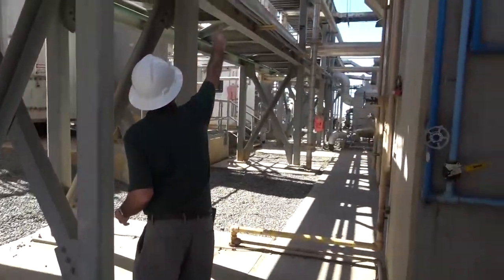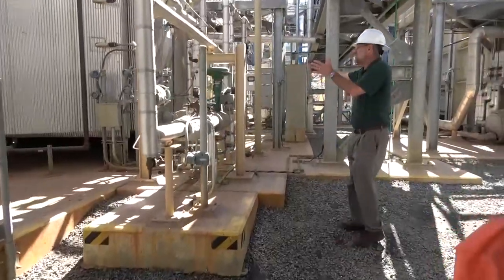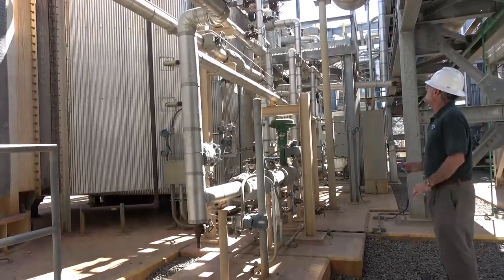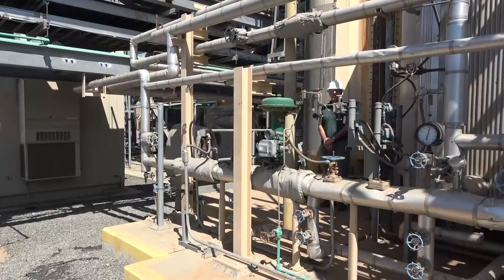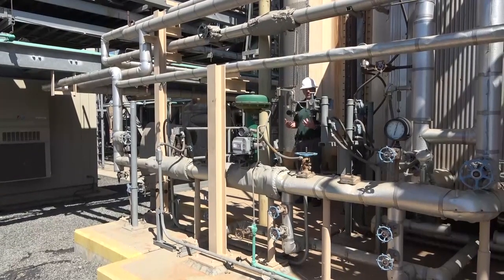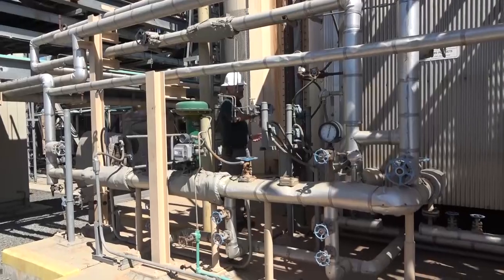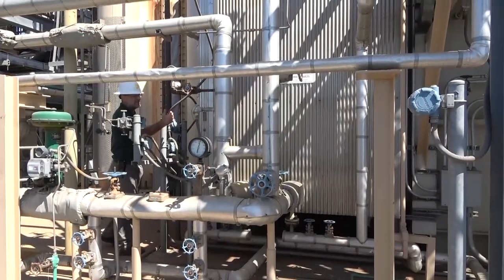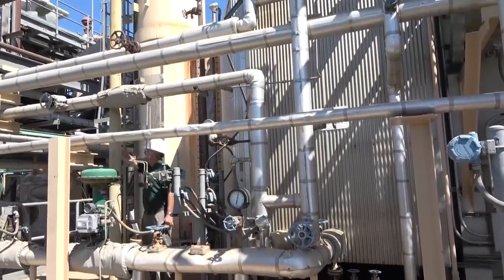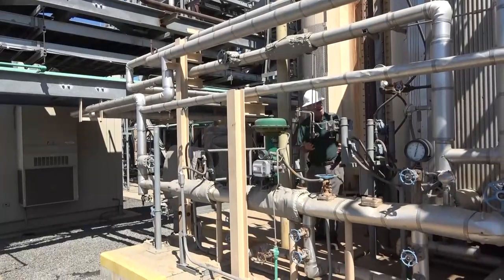The condensate is pushed out of the condensate pumps through piping and eventually to the feed water heater, which is part of the heat recovery steam generator — specifically the feed water preheater at the back of the first gas turbine. Water from the condensate pumps comes through the lines in front, moves into the heat recovery steam generator, picks up heat, and then goes up into the open feed water heater, and from there into the feed water pumps, and back over into the economizer.